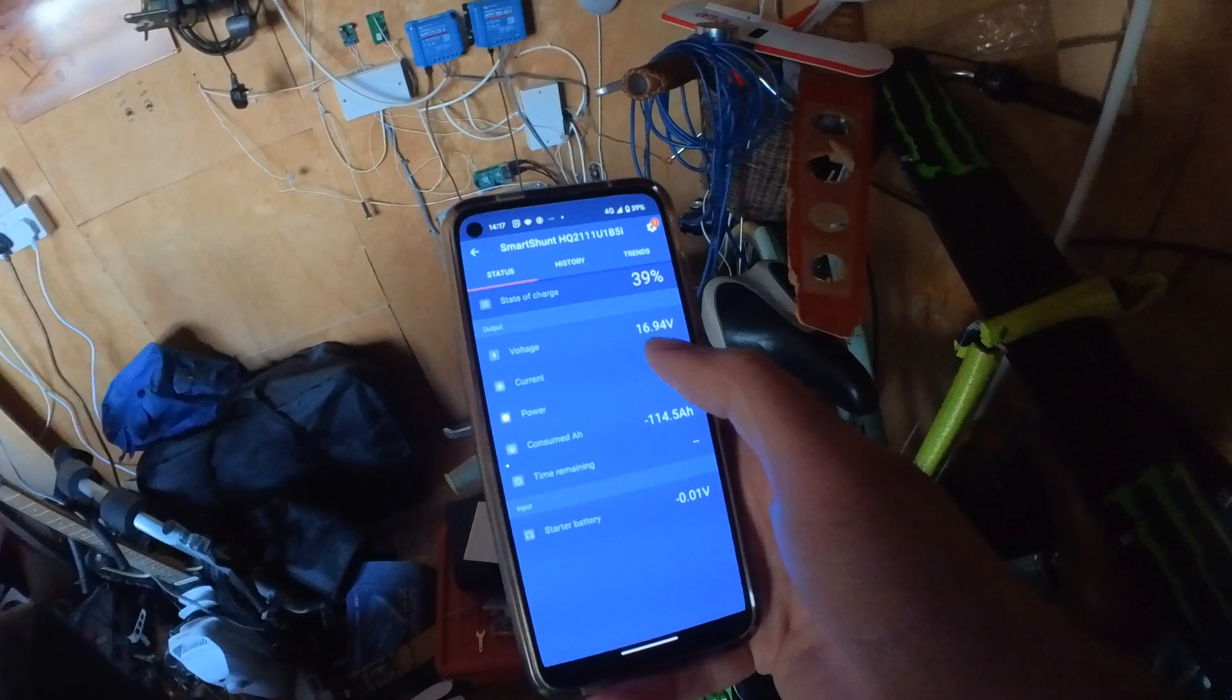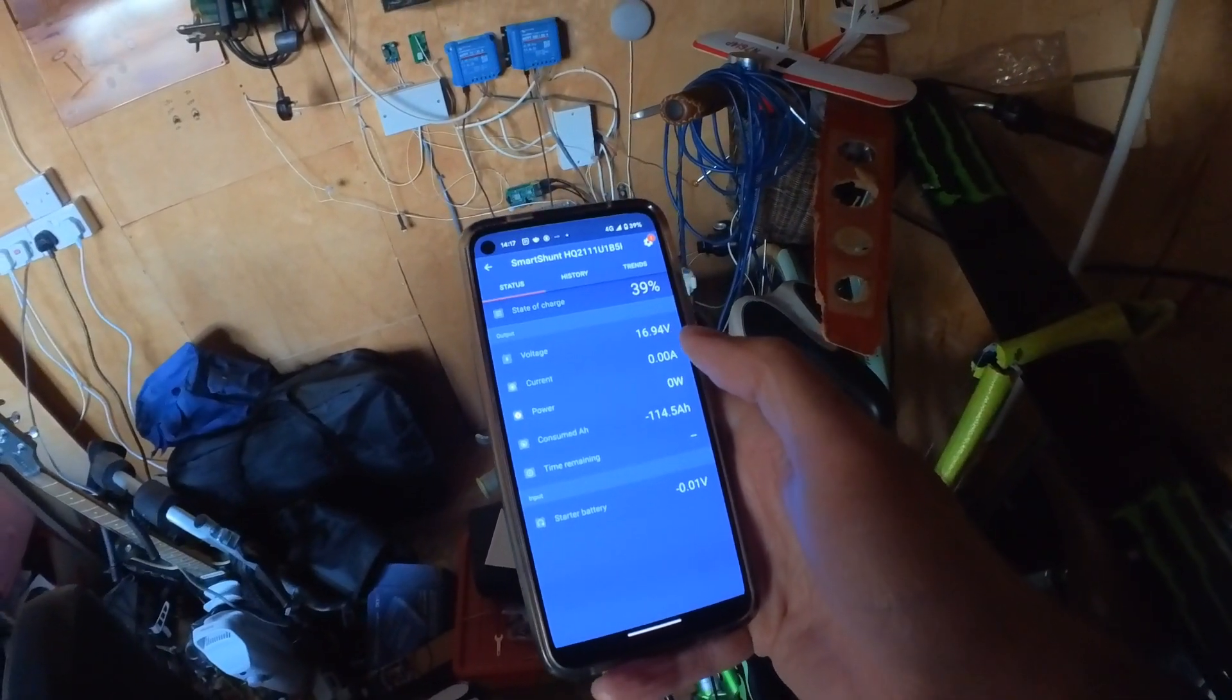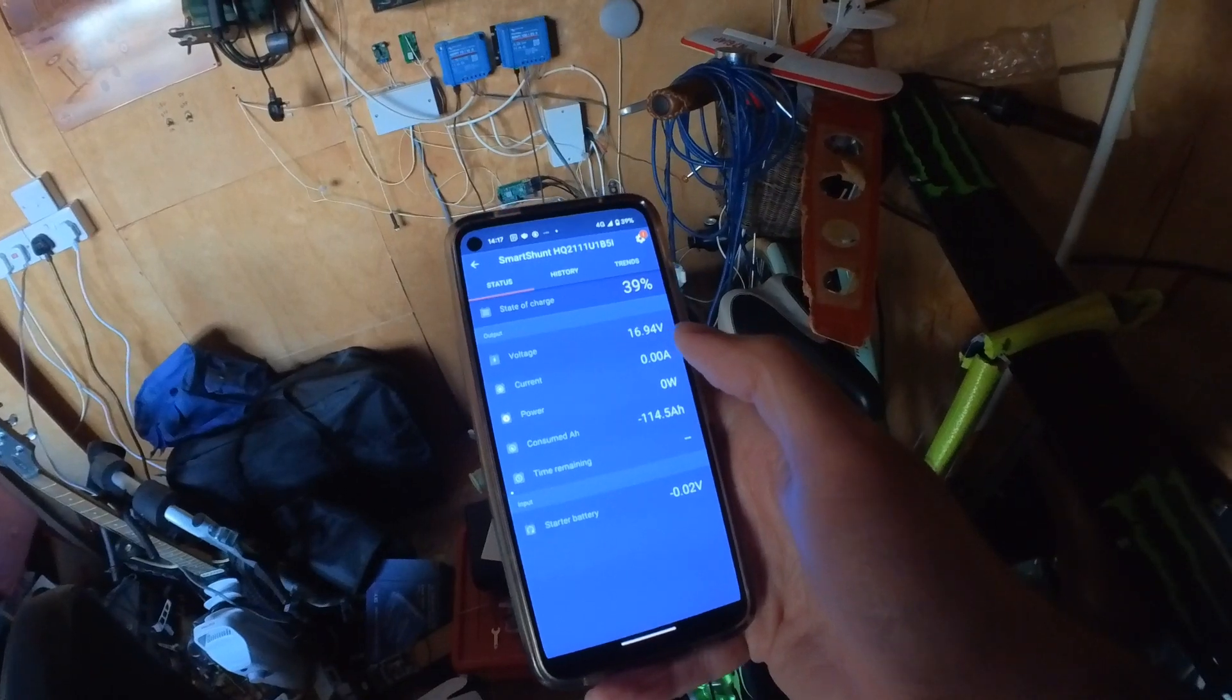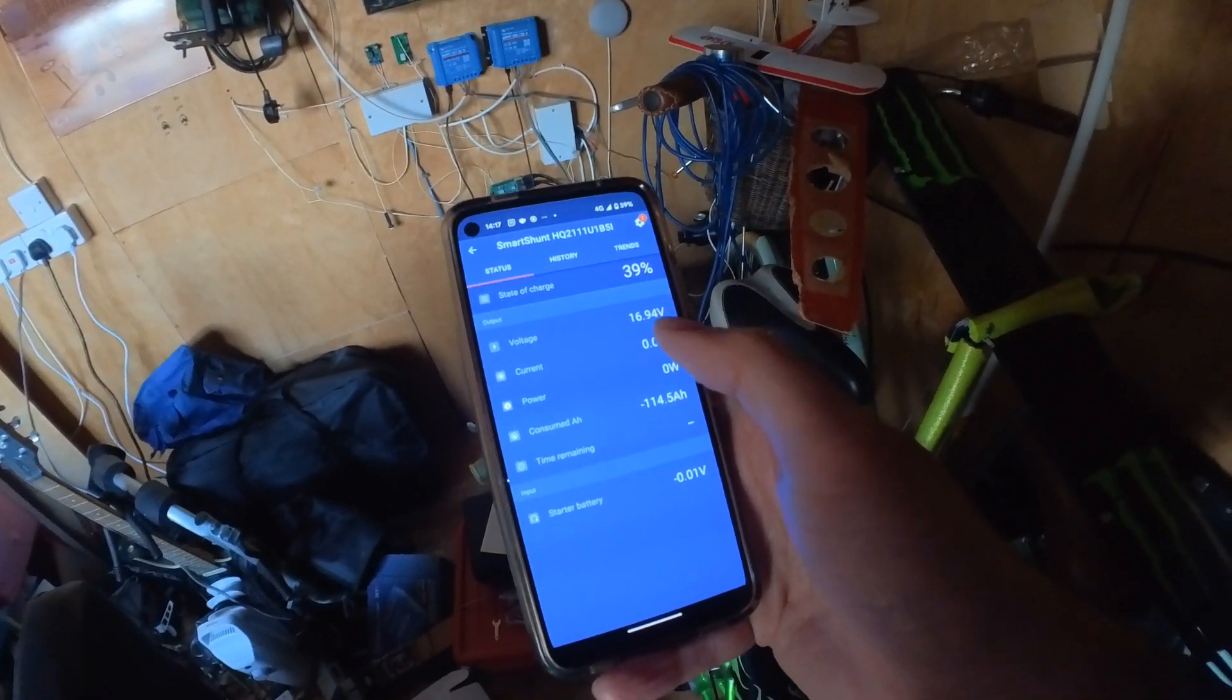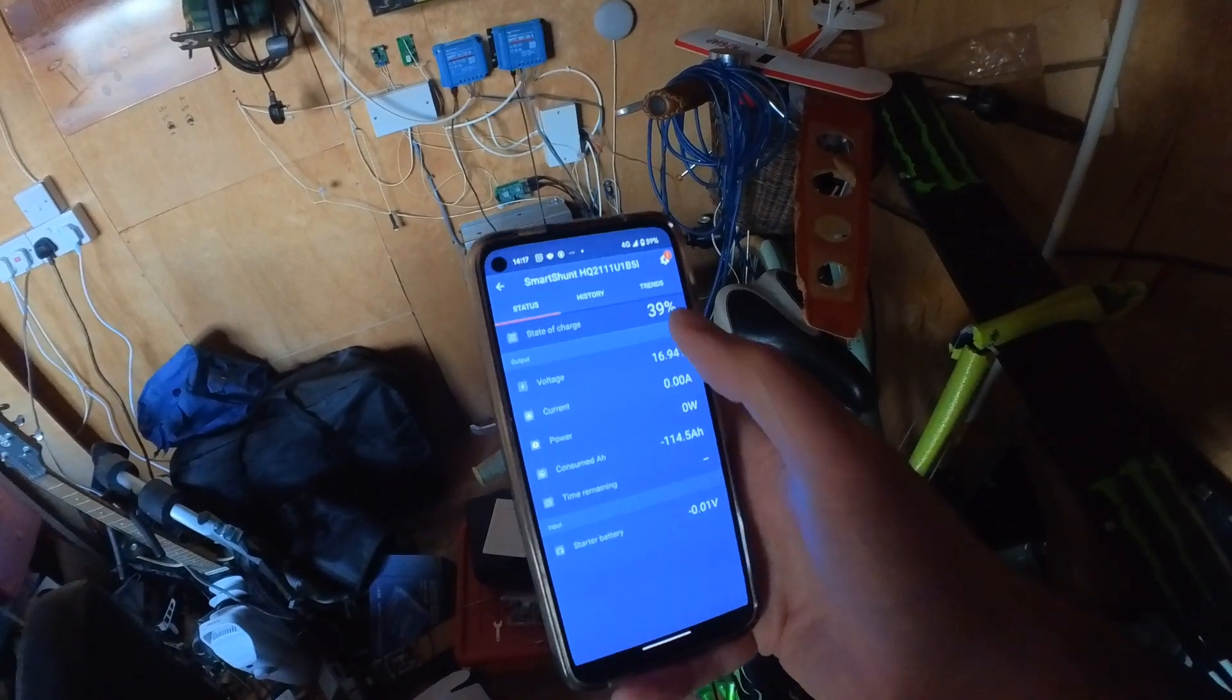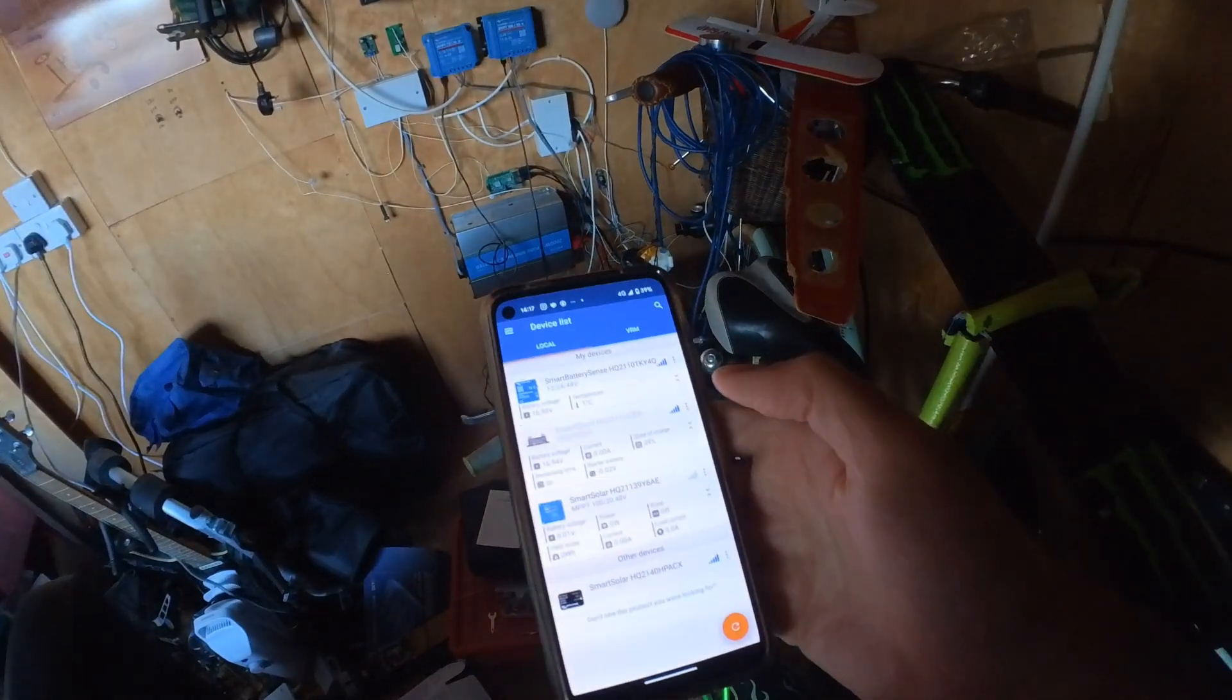Our voltage is 16.94, which is under two volts per cell. Eight cells, something like that, 16 volts. Yeah, just over two volts per cell. So these batteries are flat. That should be on zero, but I don't know why it's saying that.